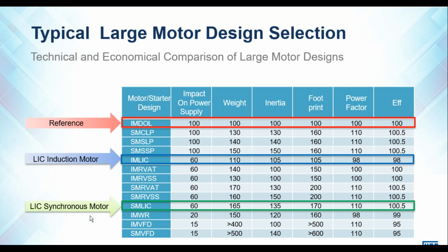We can do the same design considerations for synchronous machines. These would give the same advantage in terms of impact on the power supply. However, your weight would be significantly higher, as well as your inertia. Your footprint is almost double. Of course, we have a big advantage on a synchronous machine in that we can manipulate the power factor. Our efficiency is slightly better, but for the additional capex for a synchronous motor, it's not always a payoff benefit.